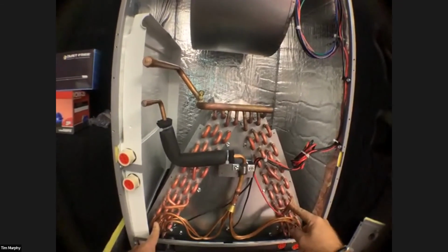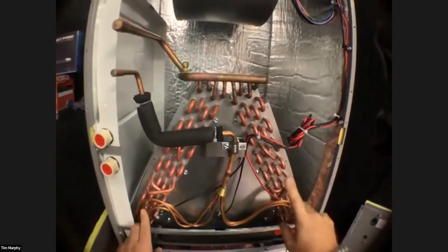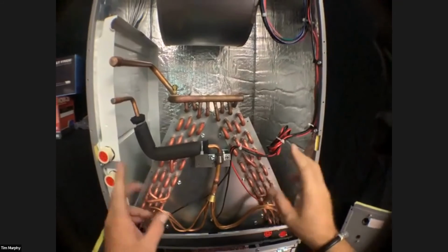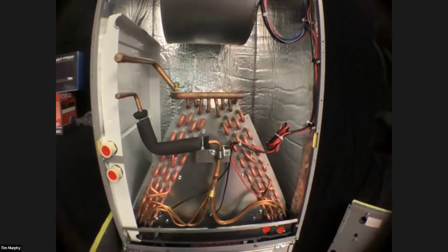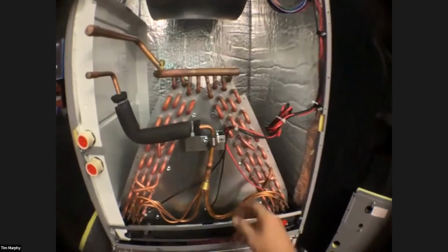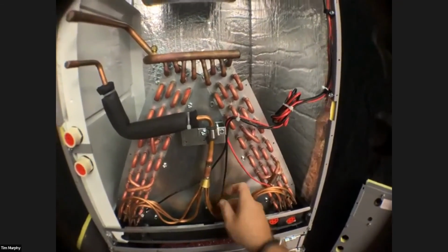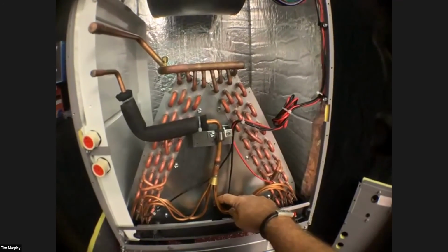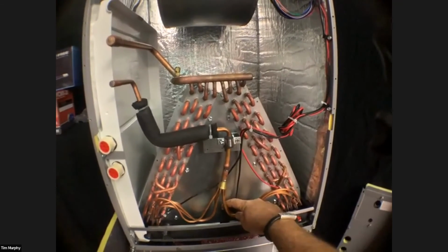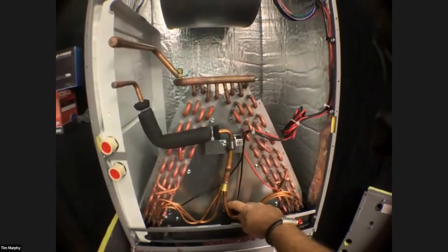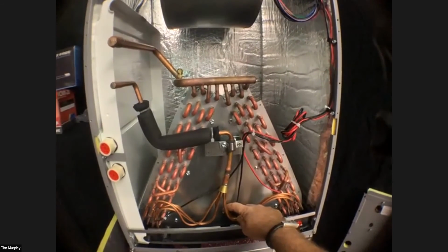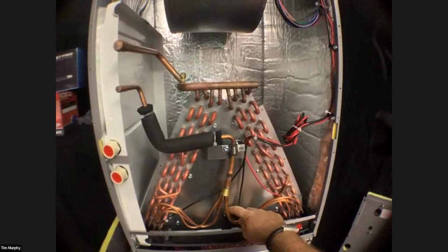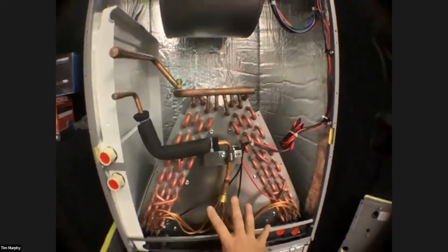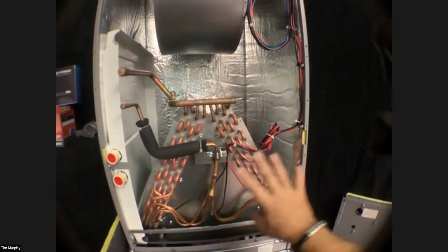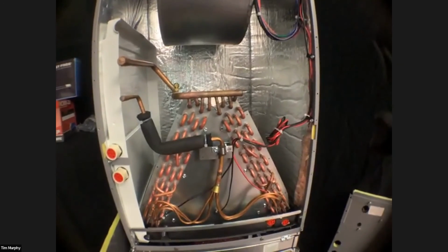You have 2 sensors on the evaporator, just like you would in a high wall mini split. You're going to have your evap in and your evap out sensors. That's going to help the system communicate back and forth with the condenser to make sure that it cools the home properly. And then you have your return air temperature sensor. The return air temperature sensor is going to be the primary source of sensing the indoor temperature, unless you go into your advanced controller and set it to sense at the advanced controller. So if you install one of these and you don't go into the settings and activate that, it's going to sense here. That may be an issue if this is in a closet and the outside area is maybe much warmer.